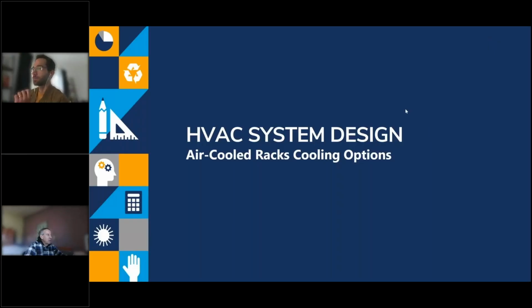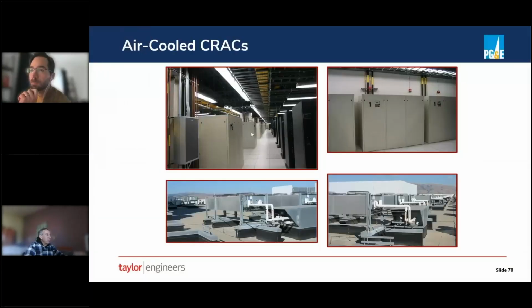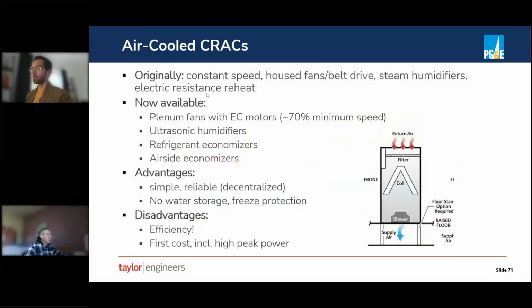Air-cooled rack cooling option. So you'll recognize or may recall this photo from way back when. This was a very early generation data center, no containment. These are CRAC units. So they're DX air conditioners, basically. And on the roof of that facility was basically just a sea of condensing units for each one of these crack units. The ones in that data center and in almost all data centers 20 years ago were constant speed. They used housed fans, belt drives. They usually had steam humidifiers and electric resistance reheat. And the humidifiers and reheat were to be able to maintain very tight humidity conditions.